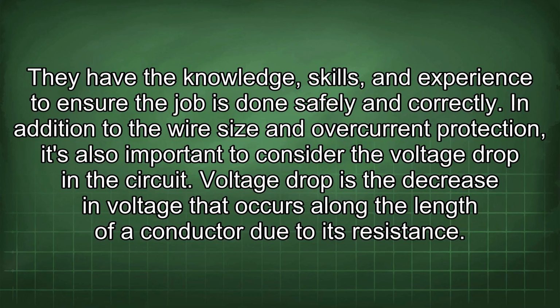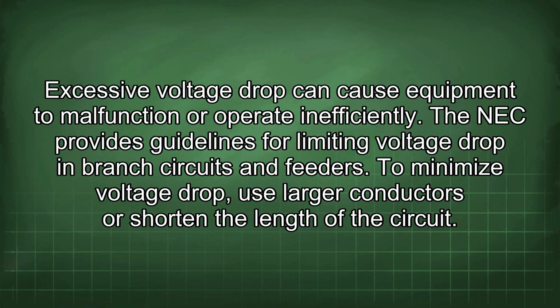In addition to the wire size and overcurrent protection, it's also important to consider the voltage drop in the circuit. Voltage drop is the decrease in voltage that occurs along the length of a conductor due to its resistance. Excessive voltage drop can cause equipment to malfunction or operate inefficiently. The NEC provides guidelines for limiting voltage drop in branch circuits and feeders. To minimize voltage drop, use larger conductors or shorten the length of the circuit.